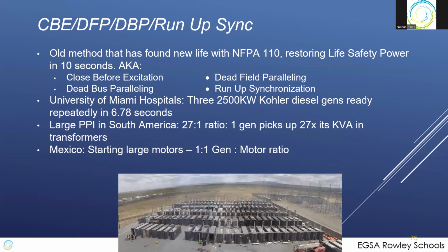It's also used at this same power plant in South America. These 480 volt machines, a bank of them, all fed transformers, and then at that medium voltage point, they were put into the substation on the right. It's a big transformer, and you couldn't energize it off one machine very well. So you soft start that transformer. You start one gen, use CBE to soft start the transformer, magnetize the transformer, if you will. Then you parallel your other machines to it. We're able to achieve a 27-to-1 ratio, so one generator can pick up 27 times its kVA in transformer, which was a huge savings to them, not having to put a transformer at each generator.